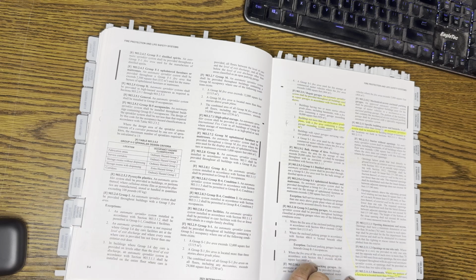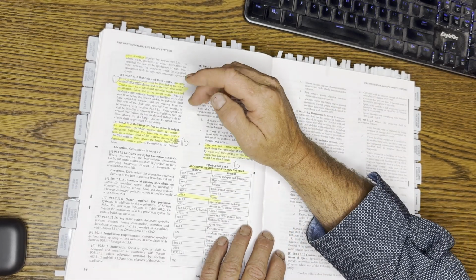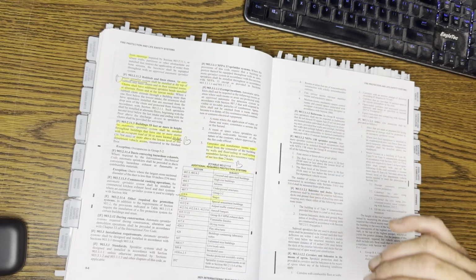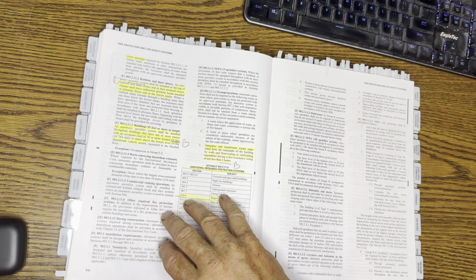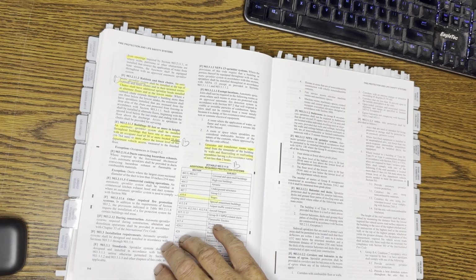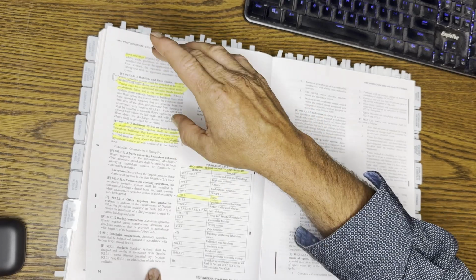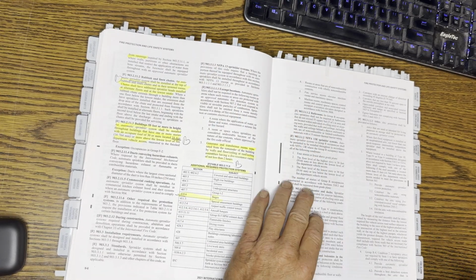This is where you're going to have, in a Group B occupancy, it's going to call out you do need suppression in certain Group B occupancies, okay, more than 55 feet, or if they have a basement location with a certain occupancy number or something like that. So just keep in mind when you're asked the question to look at section 903.2.11 for those exemptions. Otherwise, they'll get you.